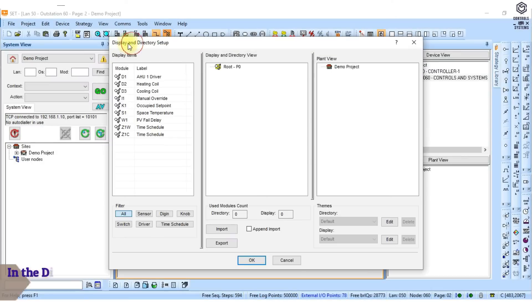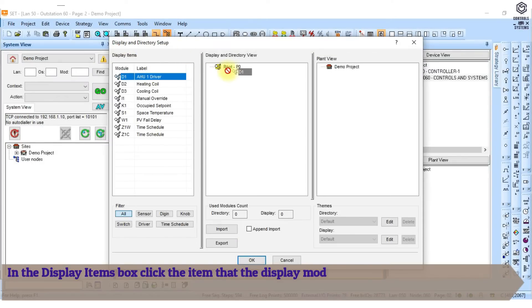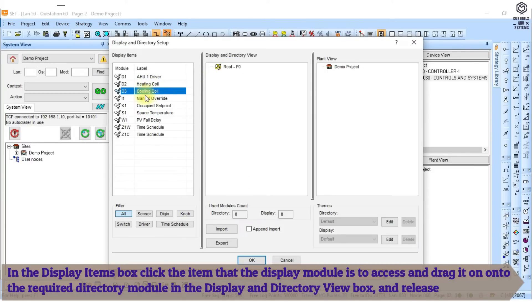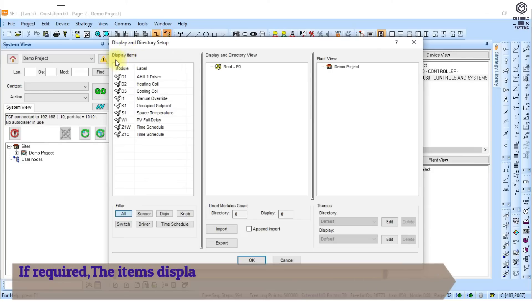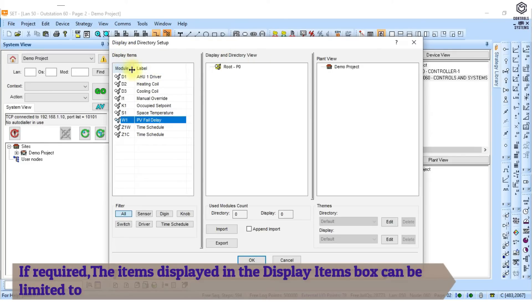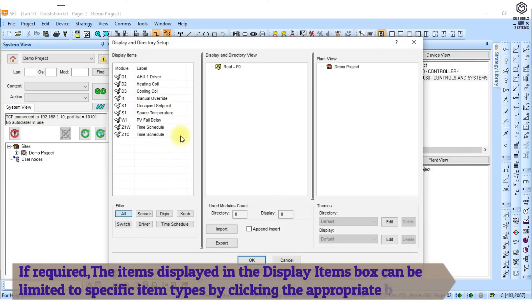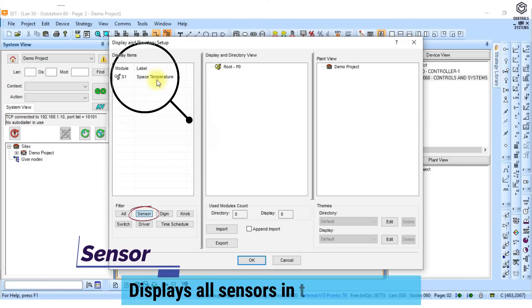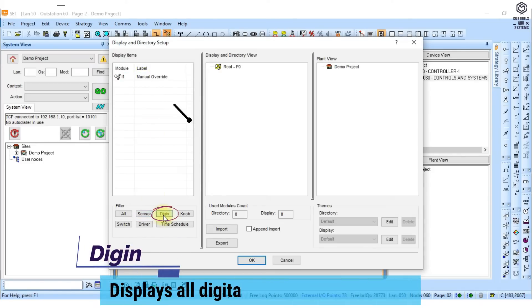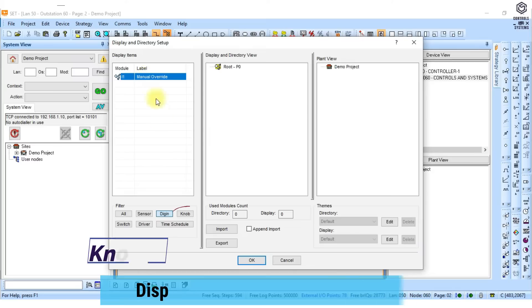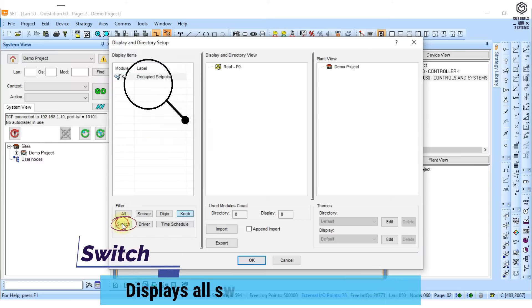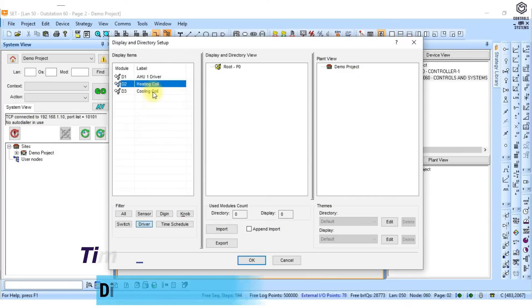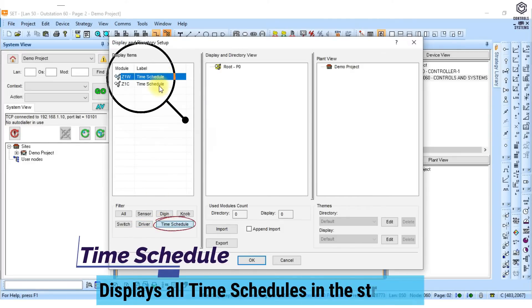Display items. In the display items box click the item that the display module is to access and drag it onto the required directory module in the display and directory view box, and release the mouse. If required, the items displayed can be limited to specific item types by clicking the appropriate button: All, Sensor, Digital inputs, Knob, Switch, Driver, or Time schedule — each displays the corresponding items in the strategy.